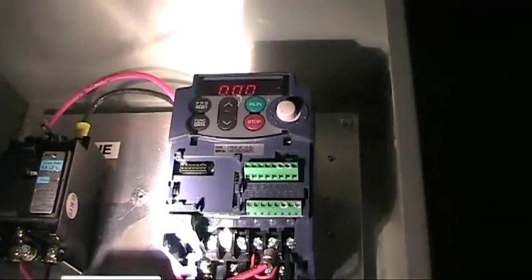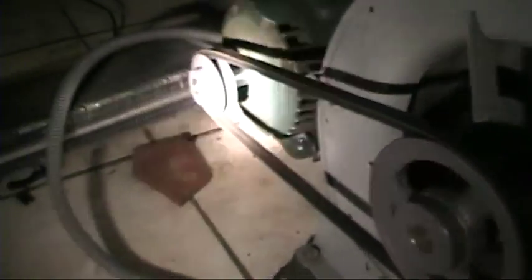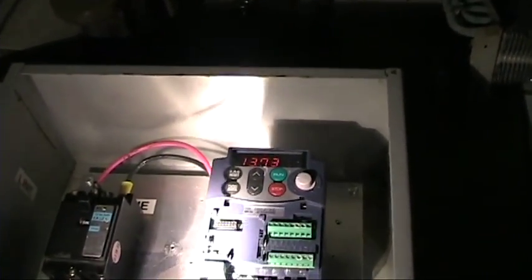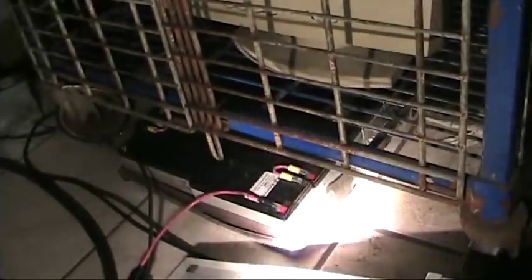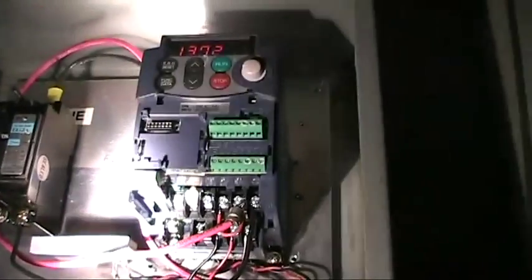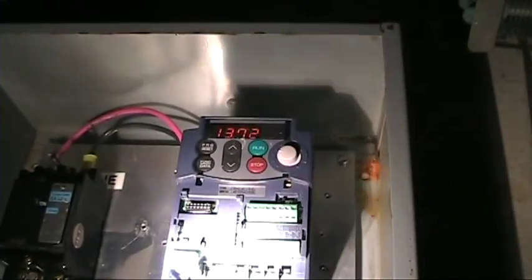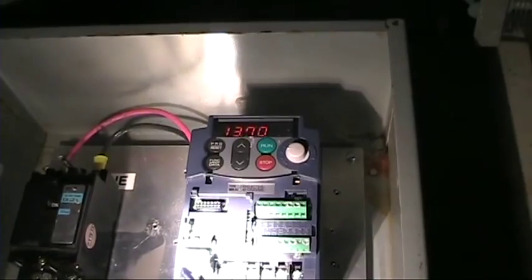So now even though the power is out, I've switched on the batteries, and we can still run the three phase motor, as you can see. And even if the power comes back on and goes off intermittently, it won't matter because the batteries will act as surge suppressors and the batteries are connected to the rectifier. So it only really gets DC power. The variable frequency drive only gets DC power. So regardless of whatever happens, power or no power, as long as a battery pack is connected, it will always work.